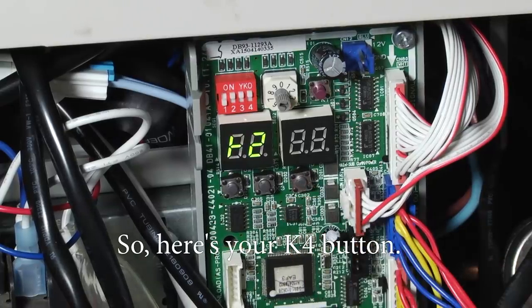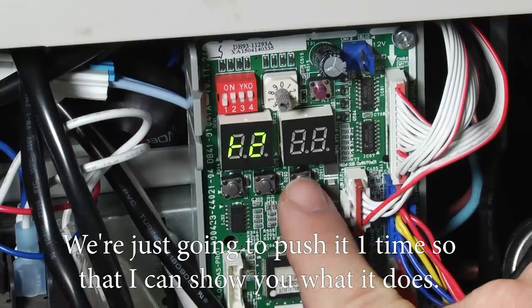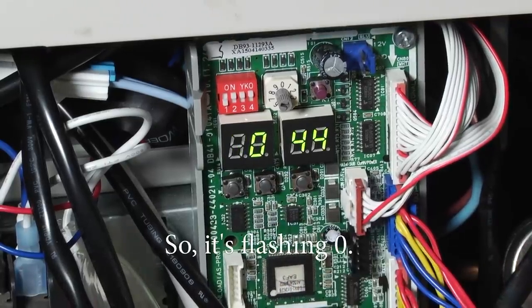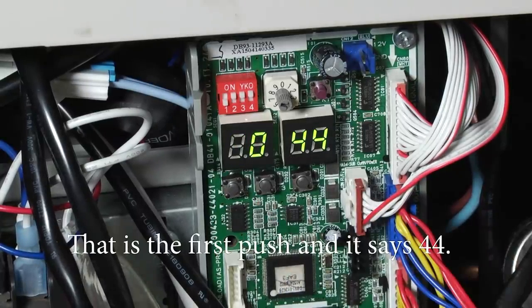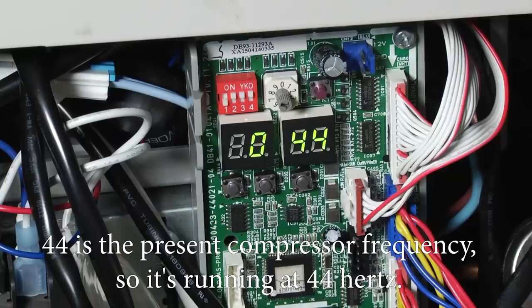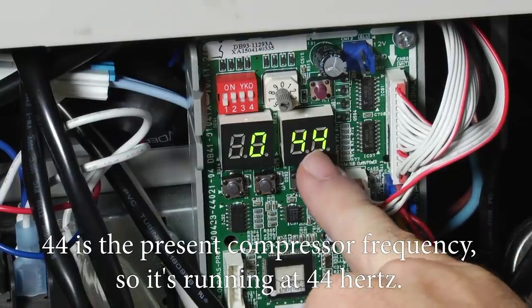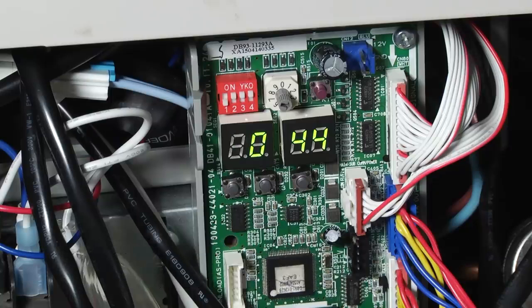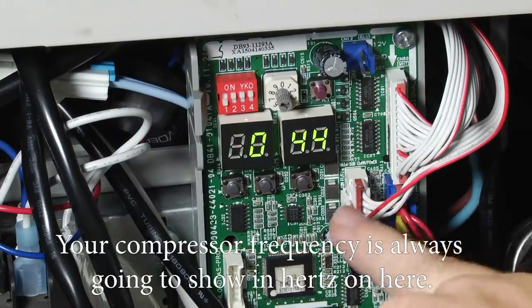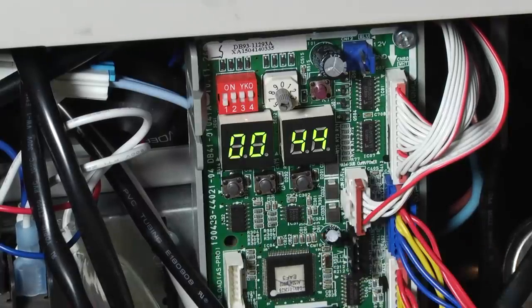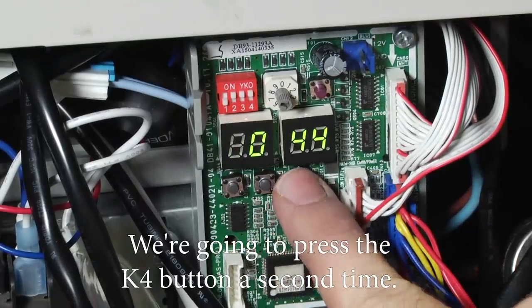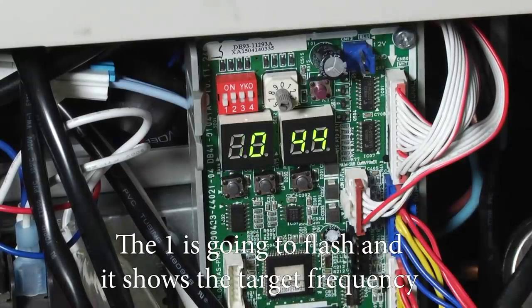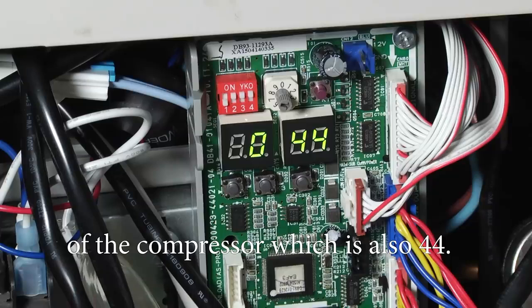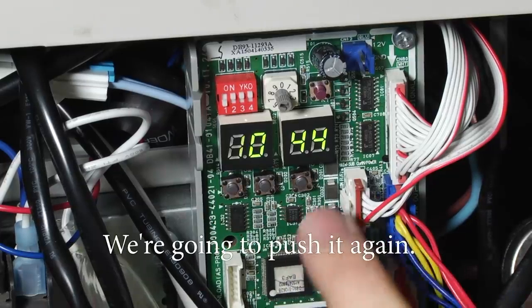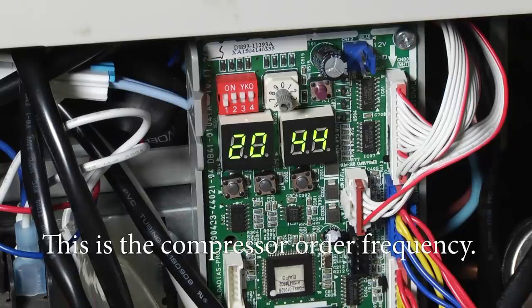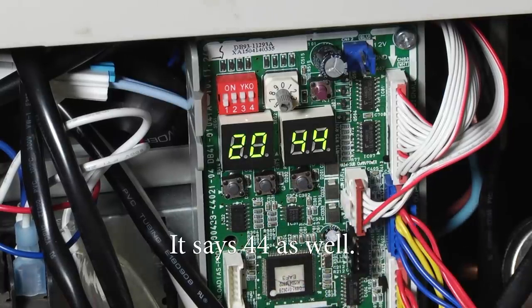So here's your K4 button. We're just going to push it one time so I can kind of show you what it does. So it's flashing 0, that is the first push, and it says 44. 44 is the present compressor frequency, so it's running at 44 hertz. Your compressor frequency is always going to show in hertz on here, so we're going to press the K4 button a second time. The 1 is going to flash and it shows the target frequency of the compressor, which is also 44. All right, we're going to push it again. This is the compressor order frequency. It says 44 as well.